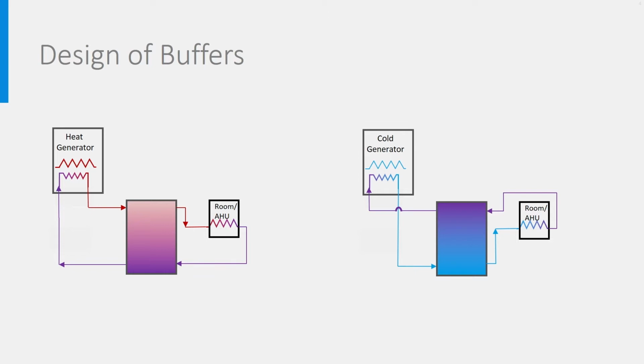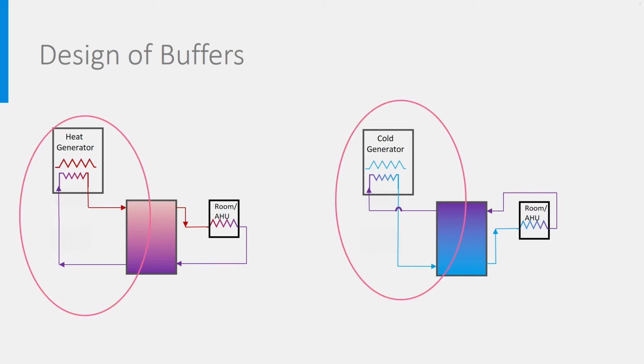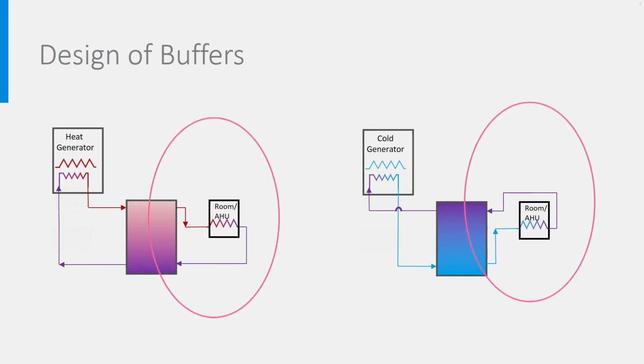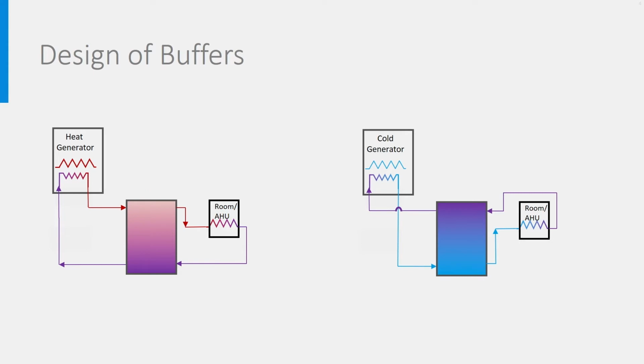Let's look at the different working modes. The generator can be on also when no heat or cold is needed, charging the tank. The generator can also be completely off, while heat and cold are provided to the rooms and the AHU. This is called tank discharge. And third, both can take place at the same time. The generator brings heat or cold to the tank, and the tank delivers simultaneously heat or cold to the emitters.